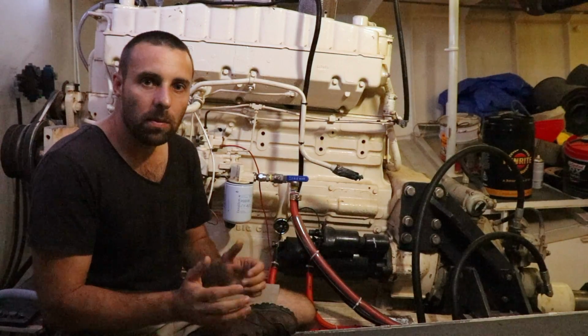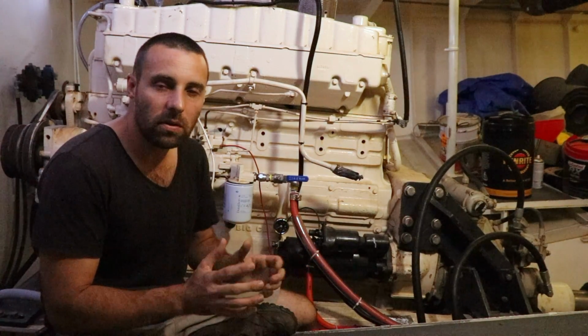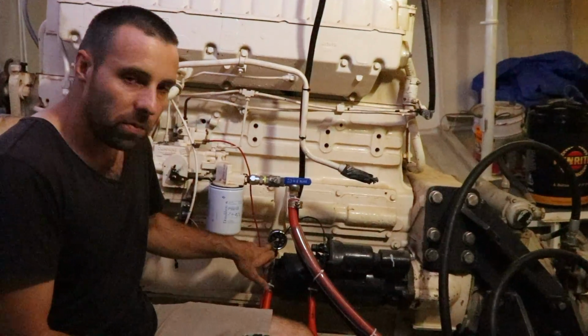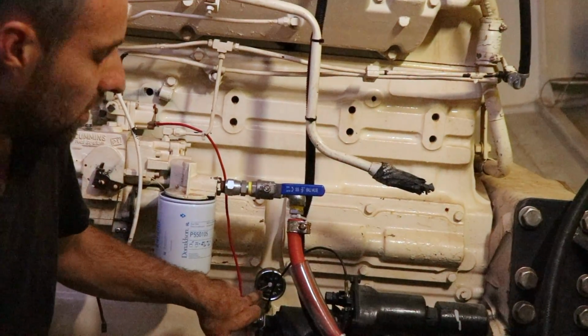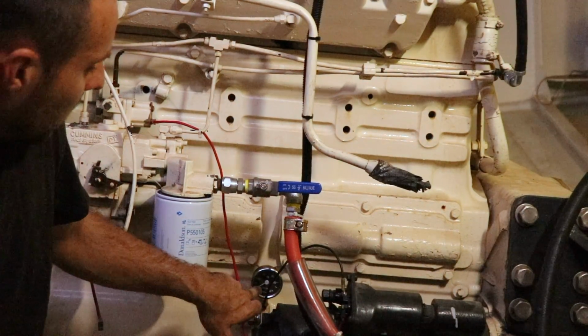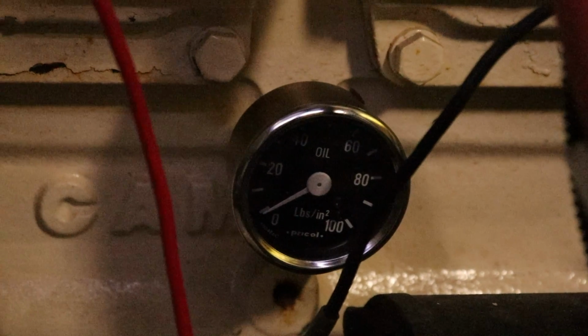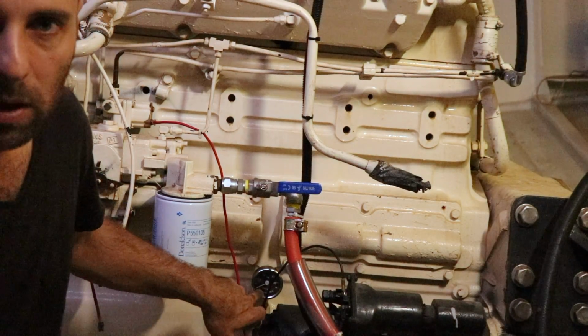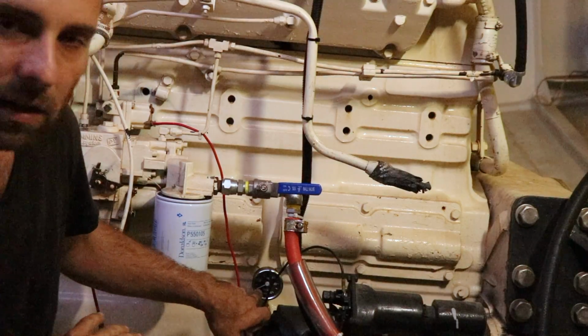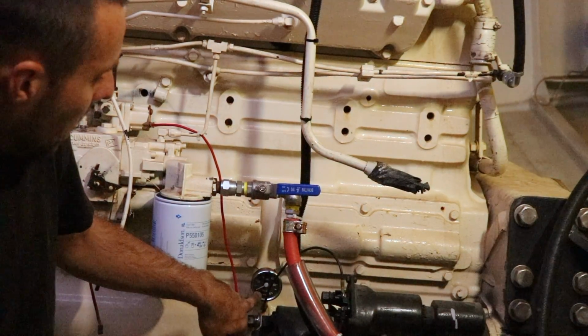On Brupeg we have a couple of ways to safeguard so we never lose that information. We've mounted an analog oil gauge directly into an oil gallery, so there's nothing in the system that can fail except that one gauge. There's one moving part in this whole system, and that tells us, independent of all other systems, how much oil pressure we have.